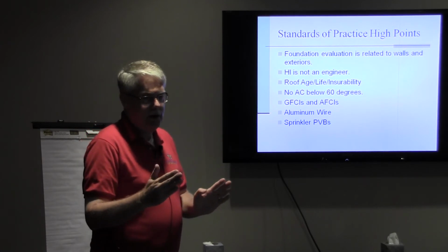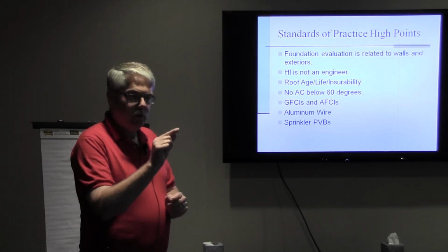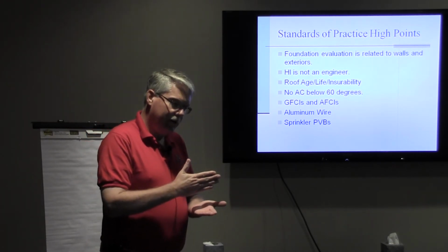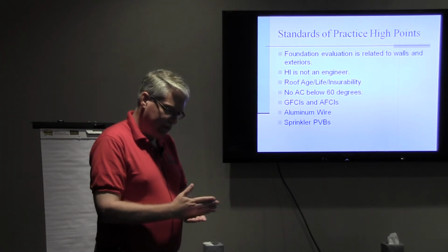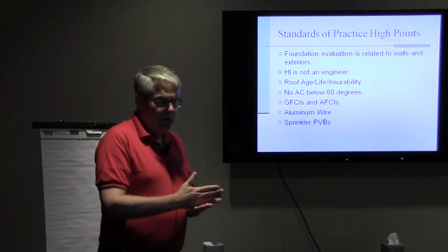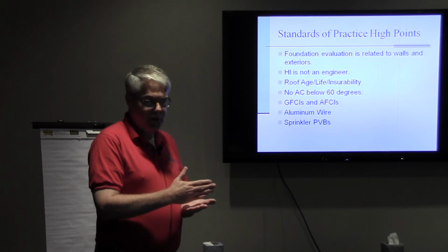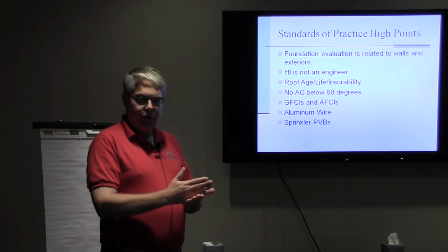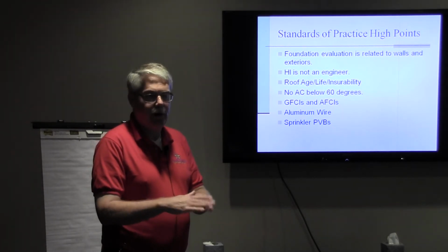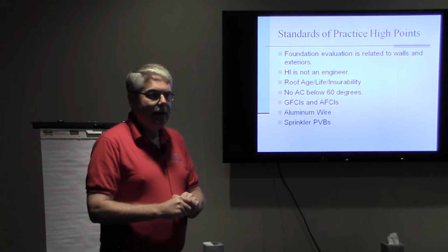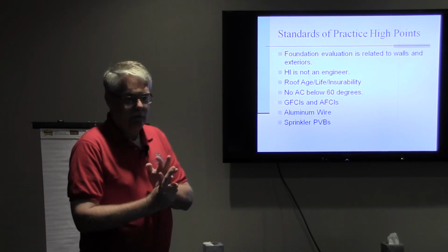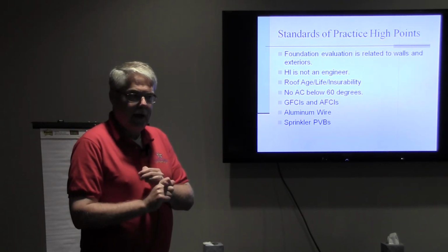Between 1981 and 1985, those outlets with the buttons in between the 2 positions, GFCIs, were added first in bathrooms, then on the exterior, which includes the garage, then in the kitchen, and then in 1996, we went from the old rule, which is only the outlets within 6 feet of the kitchen sink, to all outlets serving the counter regardless of their location. So basically, any open use outlet on the exterior, in the garage, in a bathroom, or anywhere in a kitchen counter has to be GFI protected.